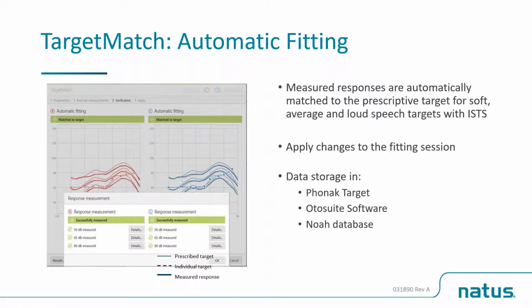This is showing you the automatic fitting option. So if I had picked to let it automatically match for the aided response targets, what's going to happen is it's going to measure the responses and then automatically work to match to the prescriptive target for the soft, average, and loud speech targets using the International Speech Test Signal, or ISTS.